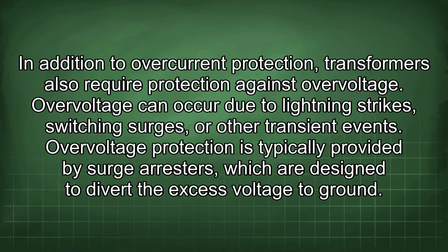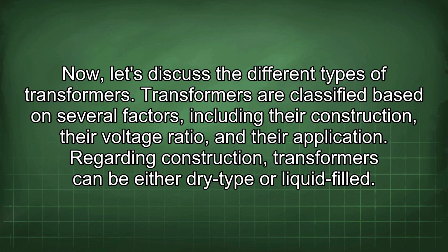In addition to overcurrent protection, transformers also require protection against overvoltage. Overvoltage can occur due to lightning strikes, switching surges, or other transient events. Overvoltage protection is typically provided by surge arresters, which are designed to divert the excess voltage to ground. Now, let's discuss the different types of transformers.